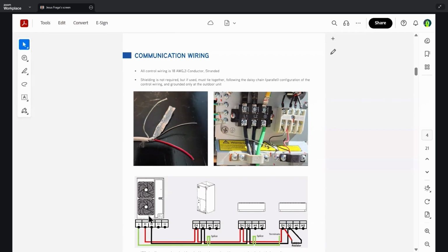So we have D1 and D2 from the outdoor unit going to the first indoor unit. From the first indoor unit, it goes to the second indoor unit, and so on and so forth. The last unit in line is going to receive the 1/4 watt, 120 ohm resistor that comes with the outdoor unit. You can place that across D1 and D2, that way you don't have any communication errors or communication faults when the system actually starts up. And you'll notice this grounded wire here. We have a splice in the first unit, a splice in the second unit, and we're going to terminate at the last unit.